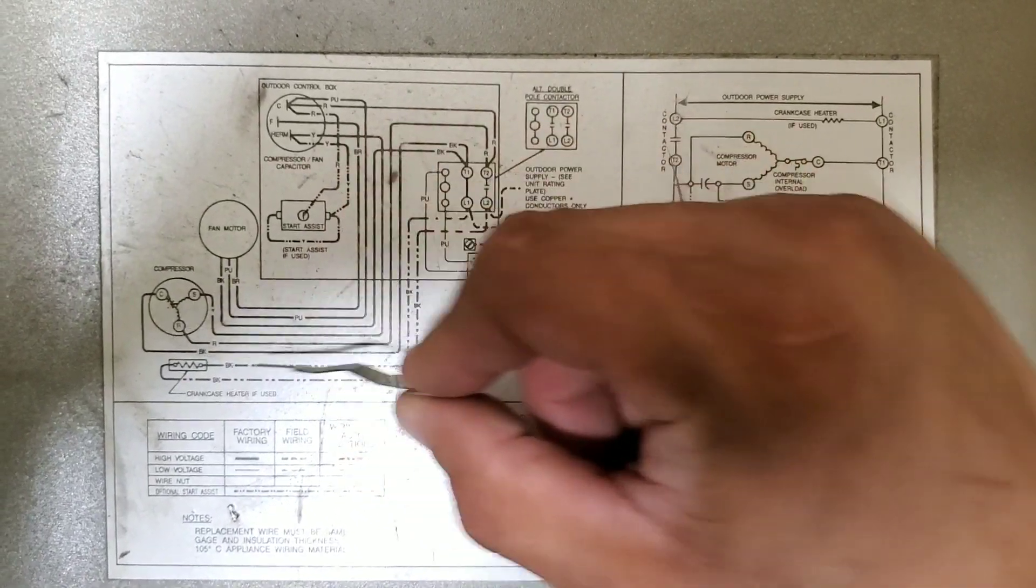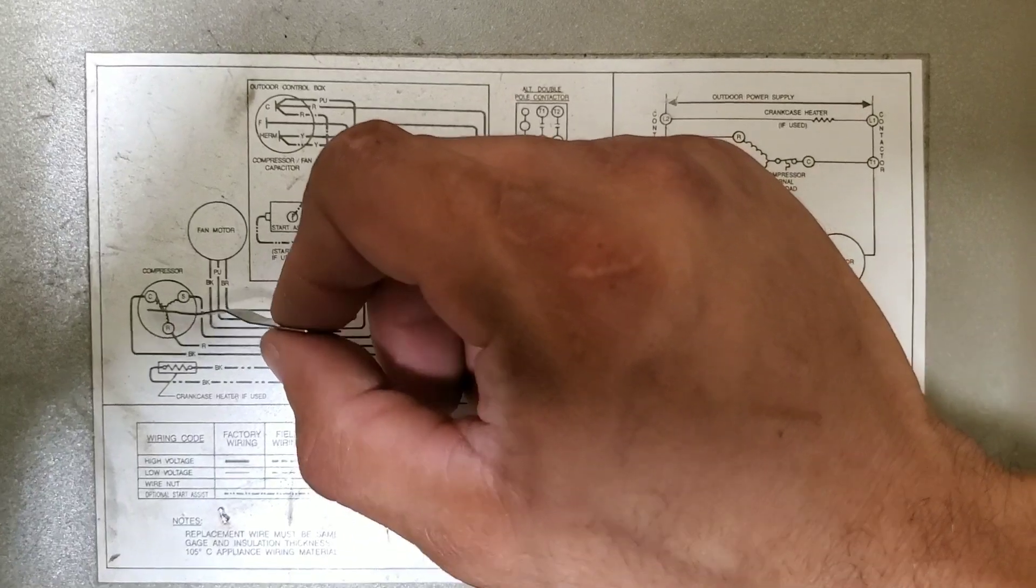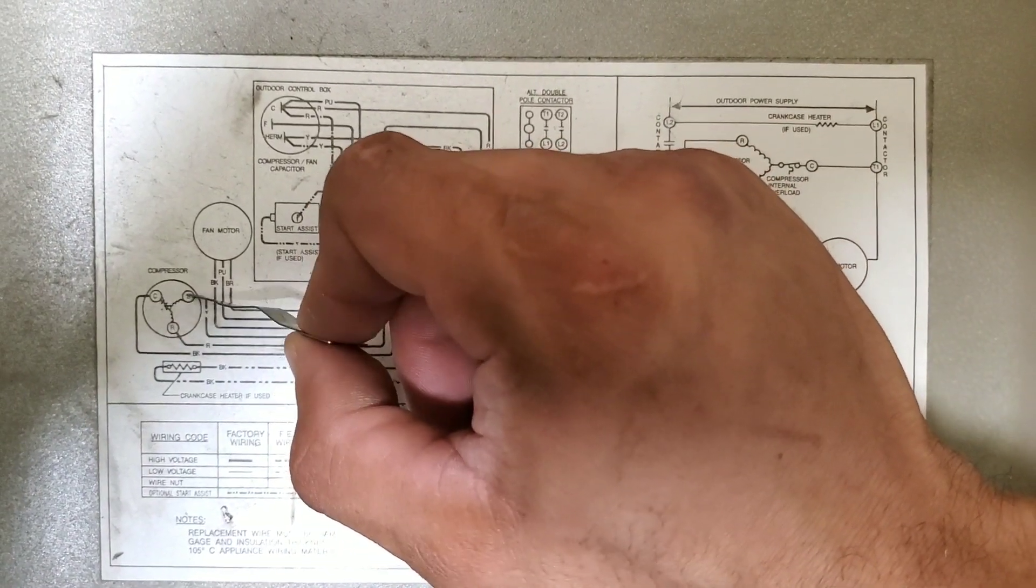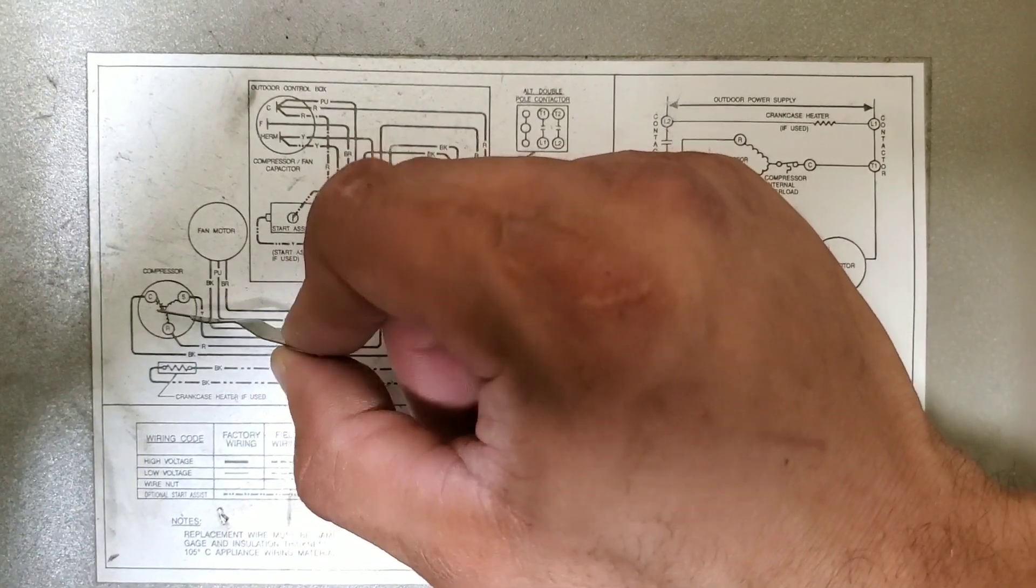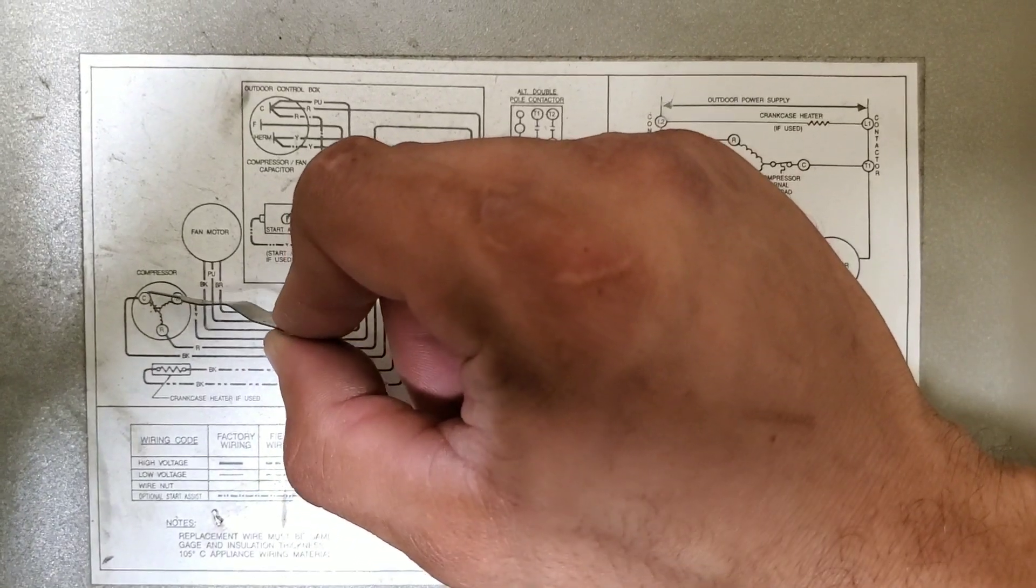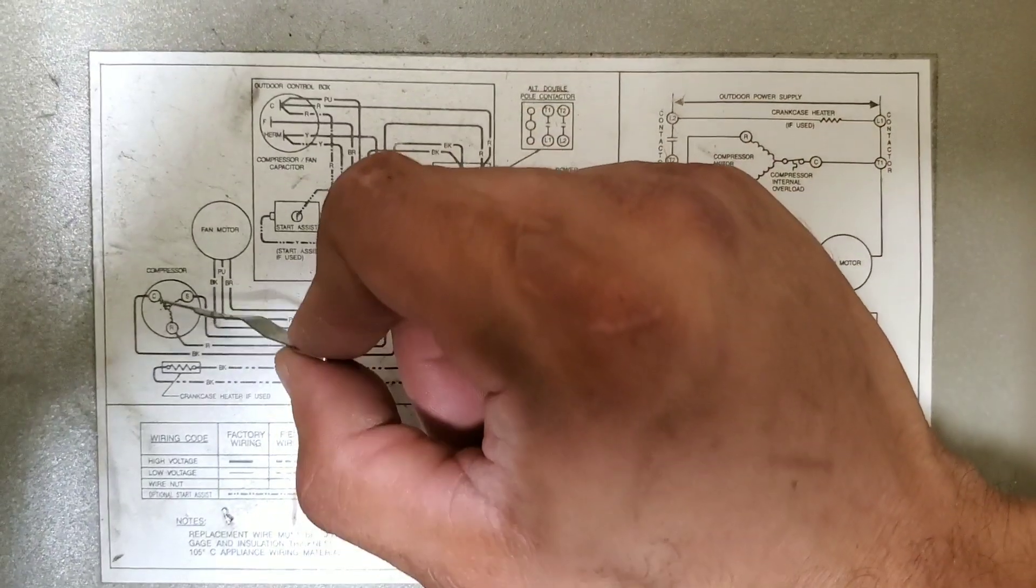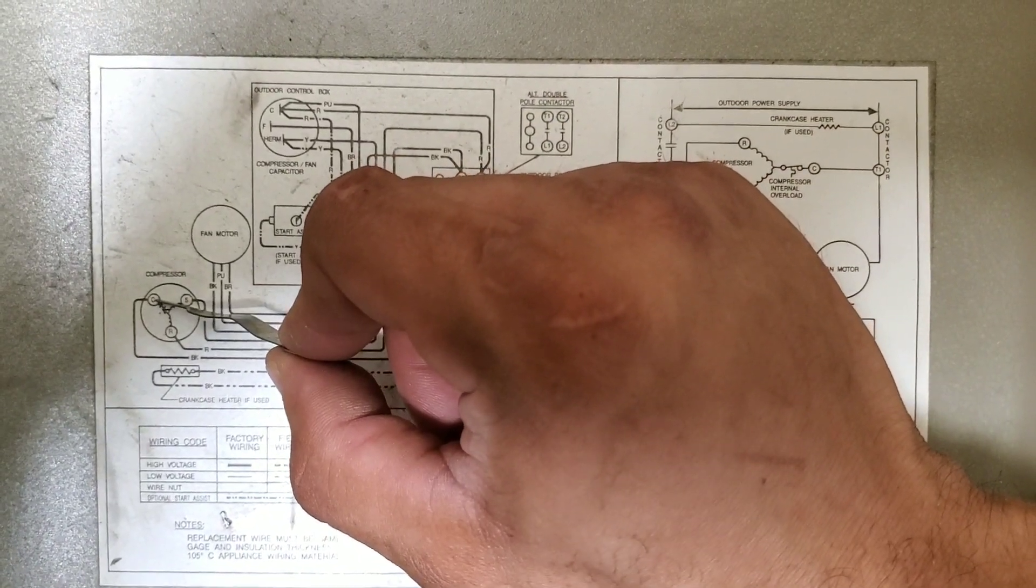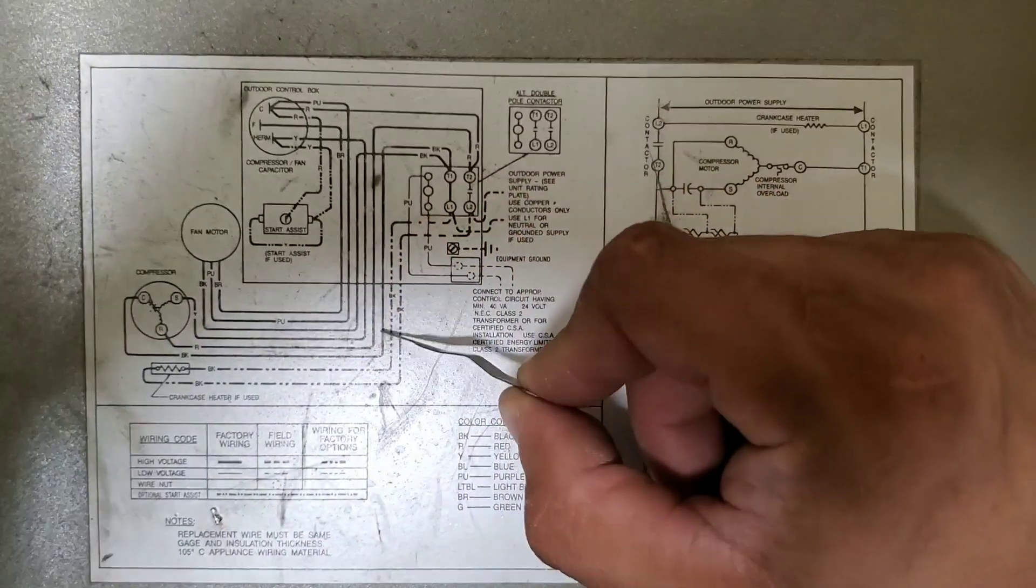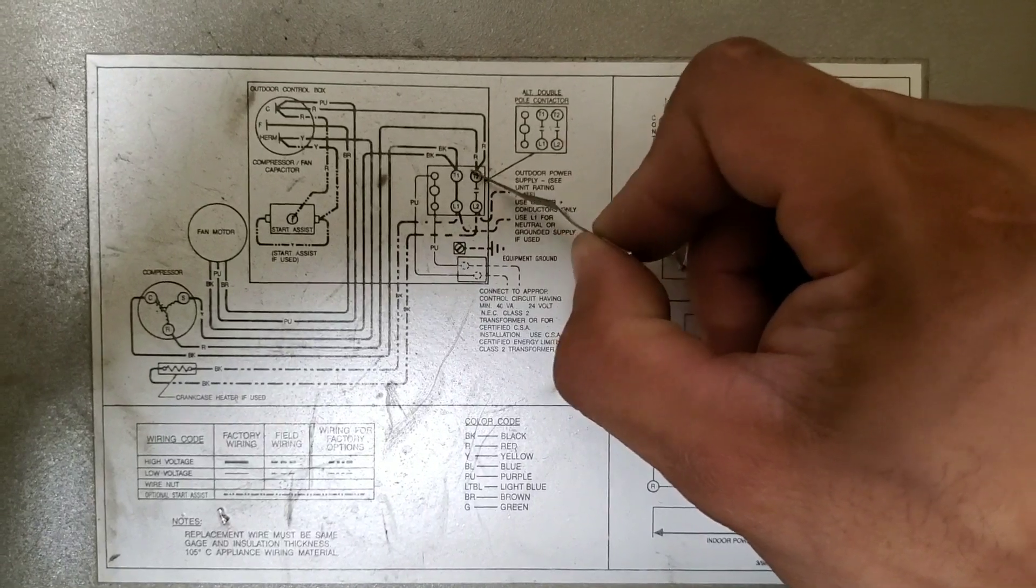The reason I decided to do this video today is because the technician working on this specific system took out the old compressor, put in the new compressor, but didn't check to see where the common, run, and start were. The new compressor we had to retrofit for this system had the common, run, and start in different positions.